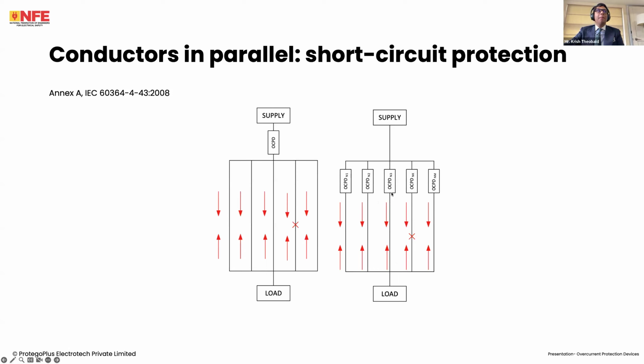So the concern is, if this happens, a short circuit occurs and disconnection occurs. If you have individual runs and individual protection of the individual runs, a short circuit will occur here, current will flow, and this OCPD may disconnect. These OCPDs may or may not disconnect. And the risk is that, because of this increased contribution of fault current from the various directions or from the various conductors, the device may not actually be able to provide protection against short circuit for the conductors. I'll show you how we look at that later on, but the point I'm trying to illustrate is that there's current flowing from all the parallel runs as well.